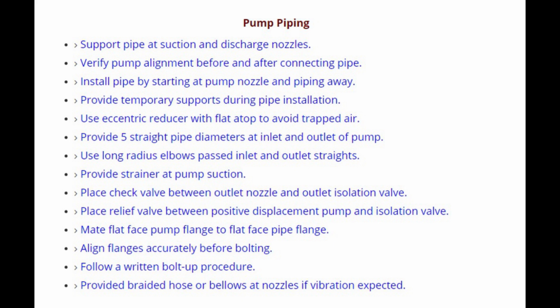Number 1. Support pipe at suction and discharge nozzles. Number 2. Verify pump alignment before and after connecting pipe. Number 3. Install pipe by starting at pump nozzle and piping away. Number 4. Provide temporary supports during pipe installation.